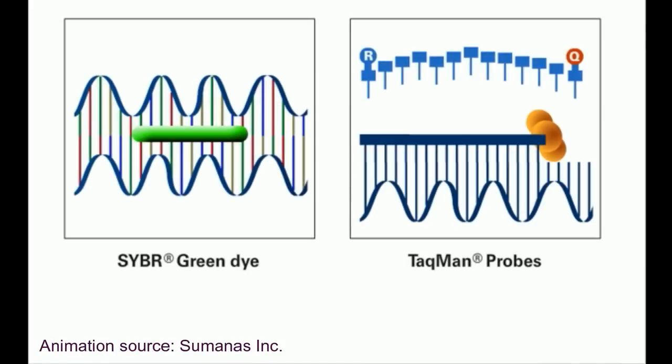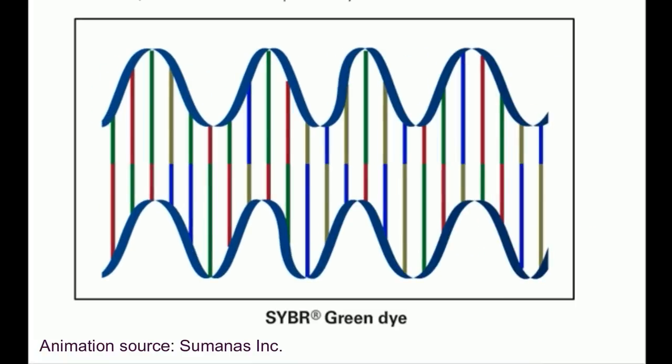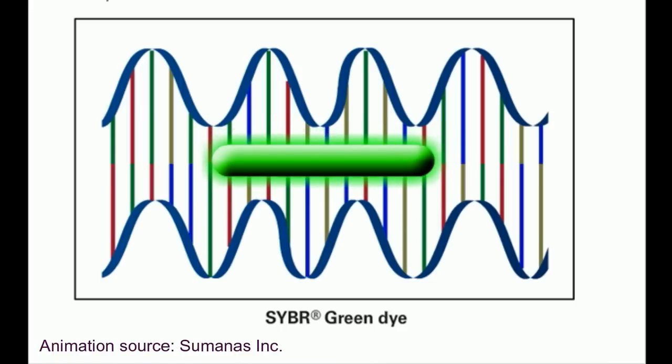Real-time PCR systems from Applied Biosystems use two main fluorescence detection methods. SYBR Green is the first one. The SYBR Green fluorescence format uses a dye called SYBR Green, which binds non-specifically to double-stranded DNA. The DNA-dye complex emits green light, which is recorded by the real-time PCR instrument.